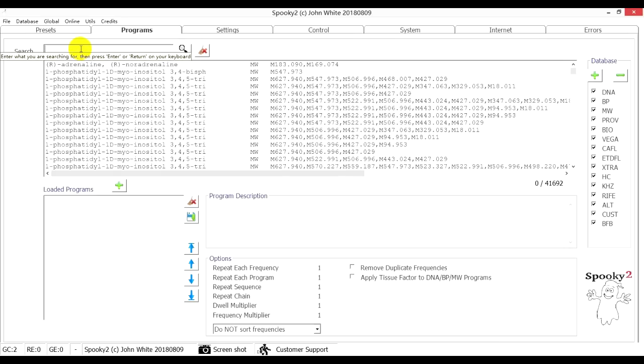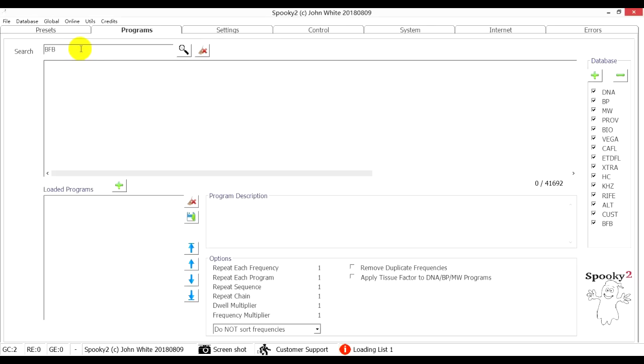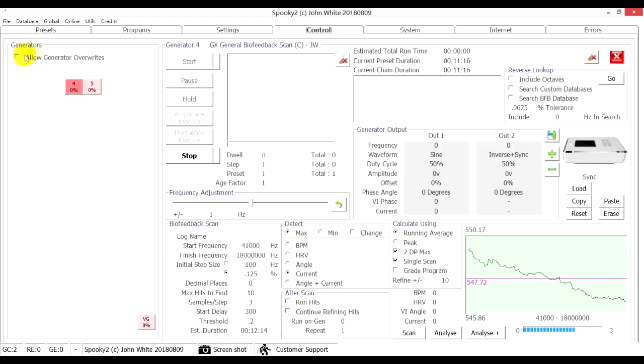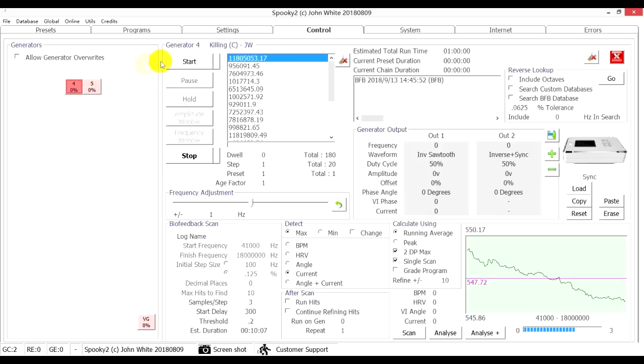Then go to the Programs tab and search BFB to find the scan results. Double-click to choose it. Go to the Control tab, tick Allow Generator Overwrites, and choose port 4 to load the program. Click the Start button to start the treatment.